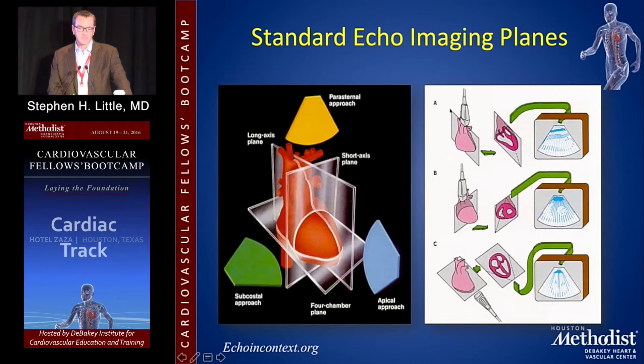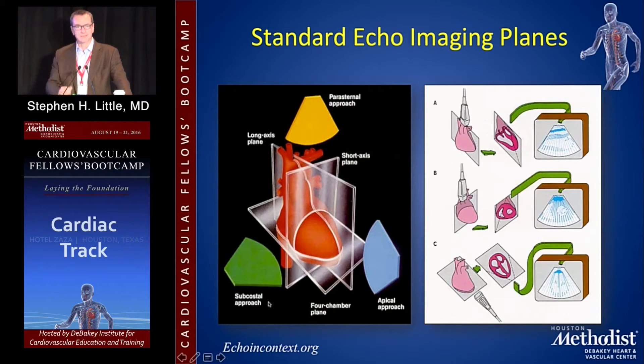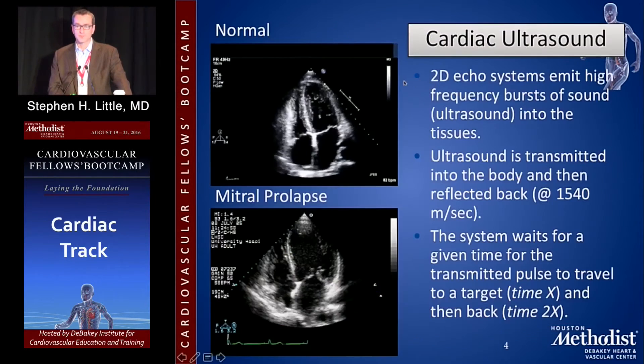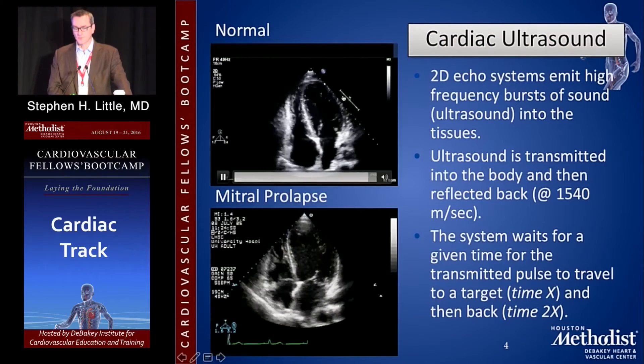The ultrasound sends off a whole series of beams along that slice plane and then tries to reconstruct the image based on how fast the ultrasound bounces back to the probe. So it knows how far it's going, when it hits something, and then looking at the change of the ultrasound frequency as it comes back, it determines the depth of what you're seeing, the shape, and whether something's moving or not.